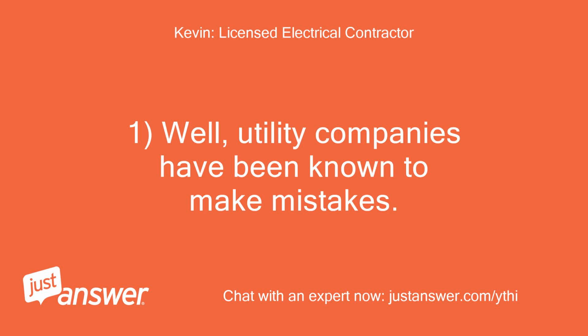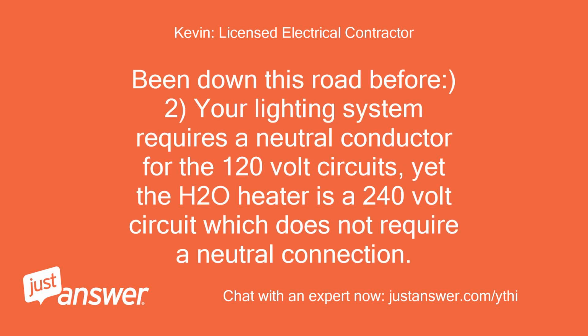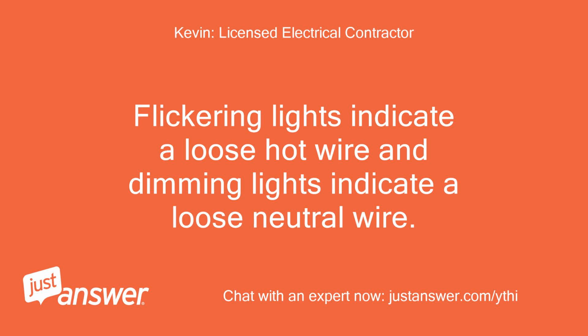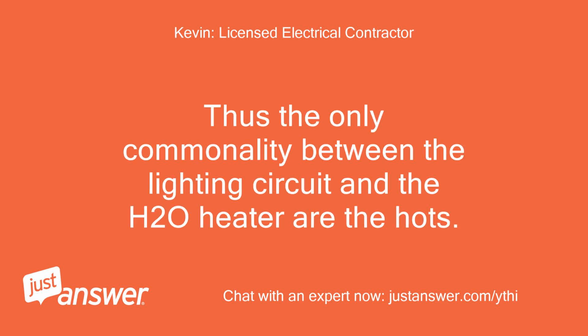1. Well, utility companies have been known to make mistakes. Been down this road before. 2. Your lighting system requires a neutral conductor for the 120 volt circuits, yet the H2O heater is a 240 volt circuit which does not require a neutral connection. Flickering lights indicate a loose hot wire and dimming lights indicate a loose neutral wire. Thus the only commonality between the lighting circuit and the H2O heater are the hots.